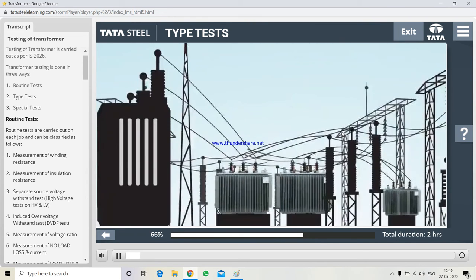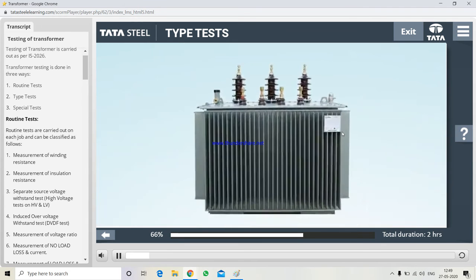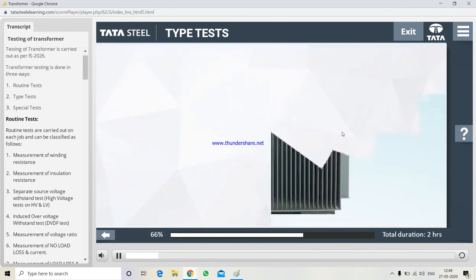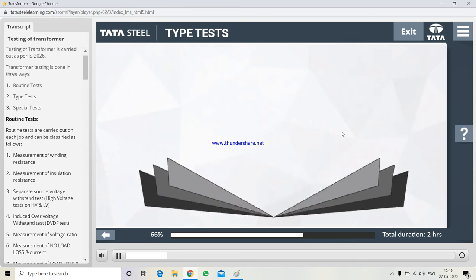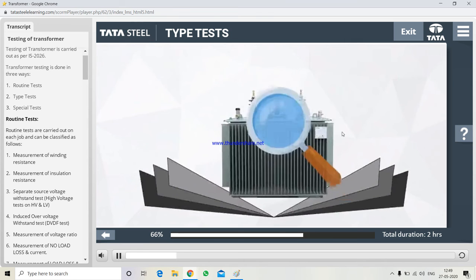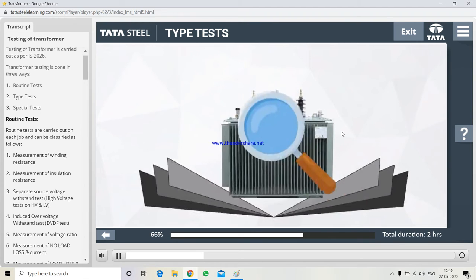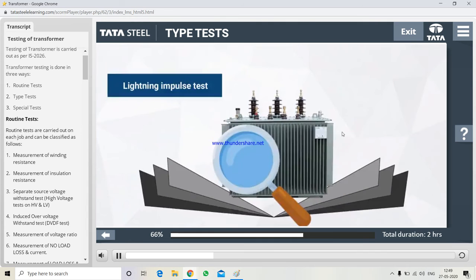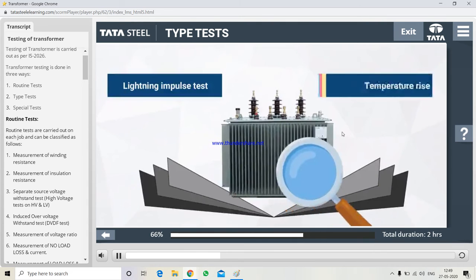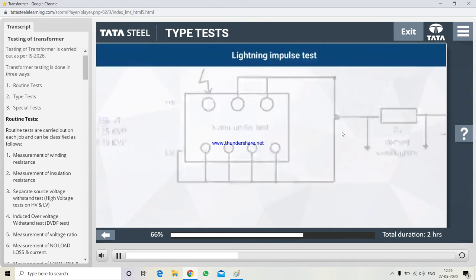Type tests are carried out only on one transformer of the lot. They are done to check the design and process parameters. They include all routine tests. Additionally, the following tests are included in type tests: 1. Lightning impulse test. 2. Temperature rise test. Lightning impulse test.